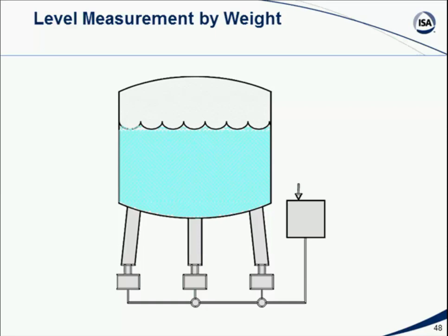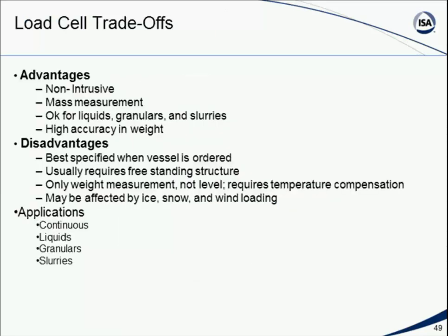So we can make a level measurement on the basis of the weight of the tank measured using things like load cells. All right, what are the good and bad things about using load cells? Well, they are non-intrusive. We don't have to stick anything in the tank, so if the tank is full of something that's terribly corrosive or nasty or pressurized, we don't care. It certainly works fine for liquids, granulars, and slurries. Now, it doesn't care what's in the tank. You want to fill the tank with puppies, you want to fill the tank with Kool-Aid, the weight will go up and we can measure it. It has a pretty good accuracy overall.